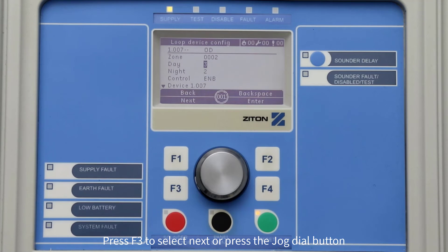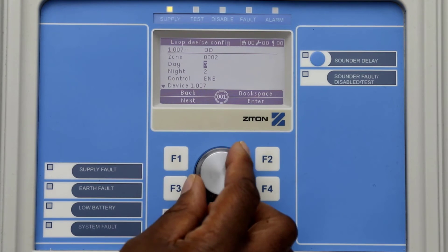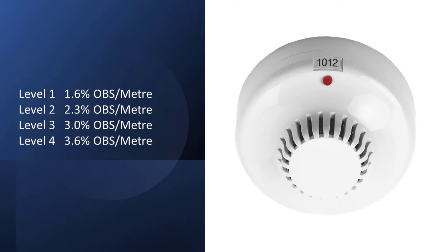For a smoke detector there are four possible daytime sensitivity settings: number one will set the device to 1.6 obscuration per meter, number two will set the device to 2.3 obscuration per meter, number three will set the device to 3.0 obscuration per meter, and number four will set the device to 3.6 obscuration per meter.